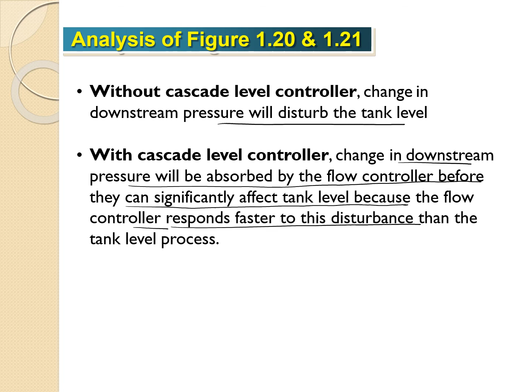Because we have to know that in the system itself, the pressure and the temperature of the surroundings inside the tank can increase or fluctuate suddenly. So to bear all these consequences, if the system is highly dynamic or highly fluctuating, we need to install this cascade control so that it can cater to all those disturbances. If the system is very simple and straightforward, there is no other external disturbance, or the system is very stable and not dynamic, then we can use the normal feedback control system.